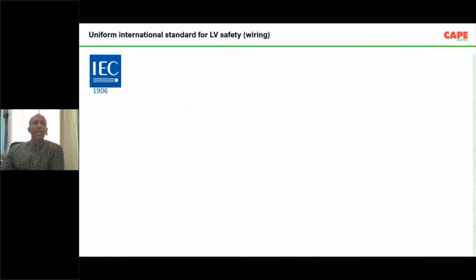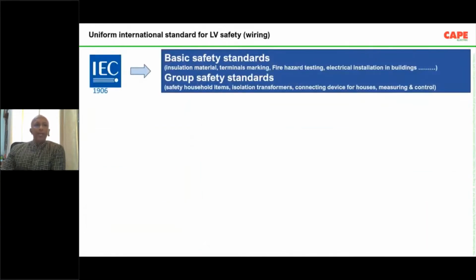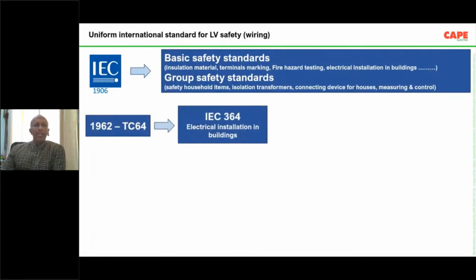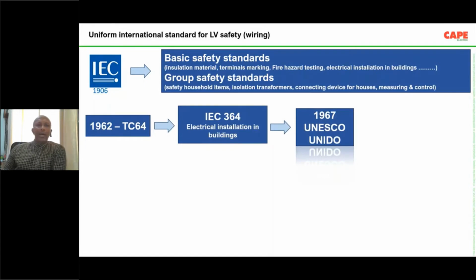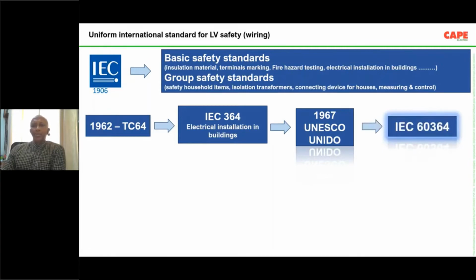Now, how do these standards originate? The International Electrotechnical Commission, IEC, in 1962 created a standards committee called TC64, and TC64 created the standard IEC 364. In 1967, there was an agreement between the United Nations and the International Electrotechnical Commission to create a standard for worldwide use. As a result, IEC created the standard IEC 60364. This standard is actually the basis for electrical safety worldwide.